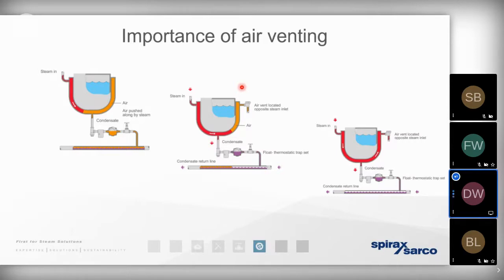So yes, we want to ensure that the air can be vented from the low point, but it's just as important to ensure that any air that has passed the condensate takeoff leg can be vented away from the high point. So that's the reason why we encourage you to think about air venting in the same breath as steam trapping, but as an entirely separate issue. If we'd failed to air vent at the top of the heat exchanger, then that's when we're putting ourselves at risk of an insulating film of air having an adverse effect on the process.